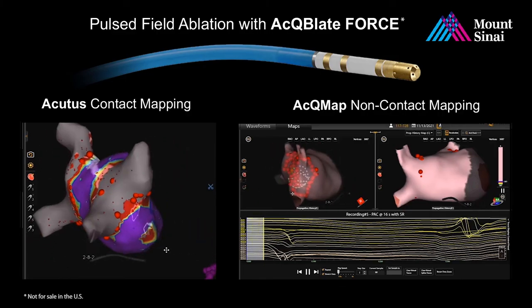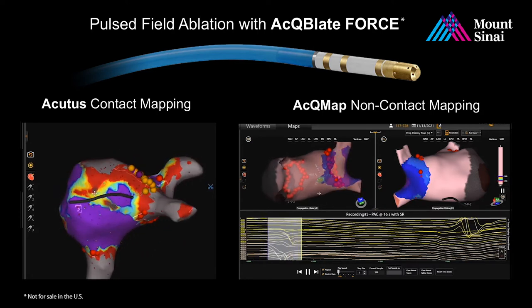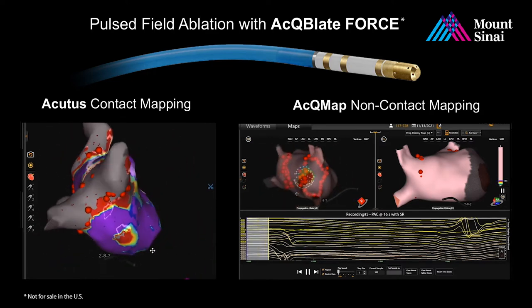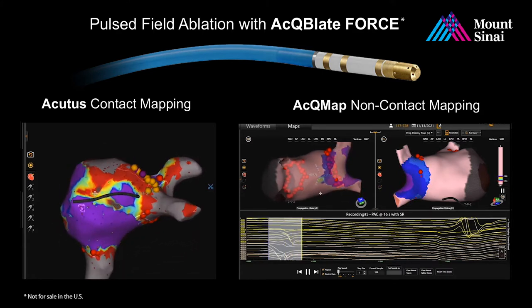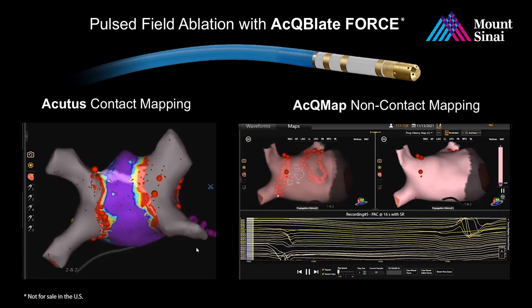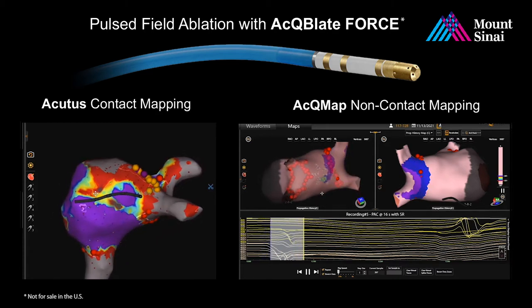As a quick introduction to the technology: the ablation catheter is a gold-tip standard catheter that goes through an eight-French sheath. The mapping system has the ability to perform either contact or non-contact mapping. In contact mapping, a traditional circular mapping catheter is swept around, anatomy is created based on electrical impedance localization, and voltage is annotated. In non-contact mapping, anatomy is generated using a basket catheter where each node contains an ultrasound crystal — based on distances seen on those ultrasound crystals, the left atrial anatomy is generated and far-field electrical information is projected onto it.